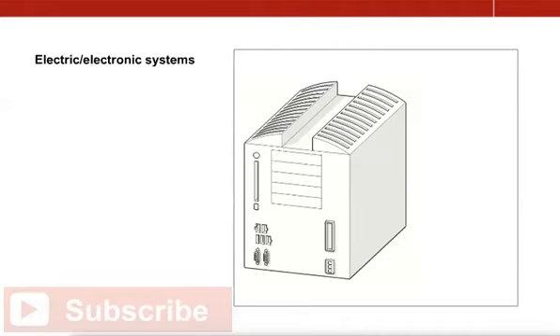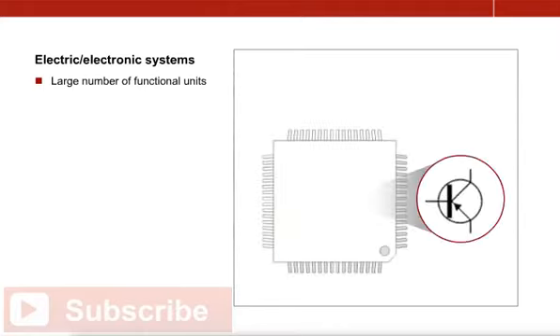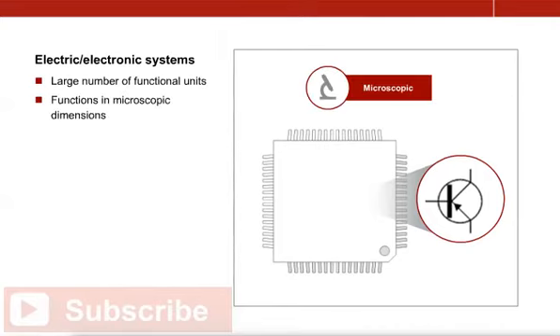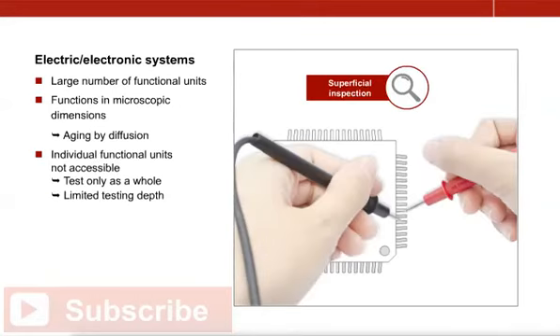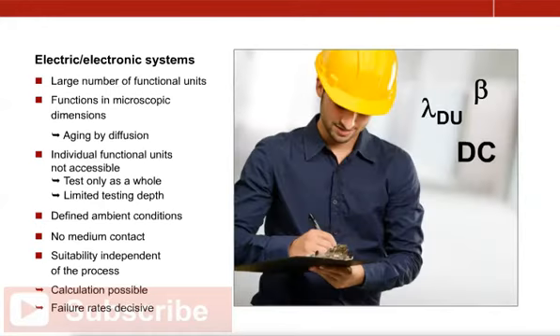In electronic systems such as programmable logic controllers, a single component often comprises a number of functional units, which, like the transistors in an integrated circuit, are microscopic in size. In this case, aging and failure are mainly caused by diffusion processes that occur on the atomic level. Only the component as a whole, and not the individual functional units, can be tested, which means that the testing depth is limited. However, such systems are mainly used in a defined environment, without contact with the process medium. As a result, their suitability does not depend on the process conditions. This is why failures can conveniently be described statistically.